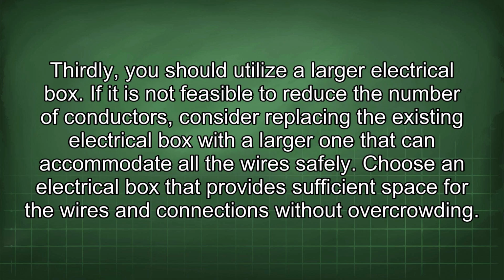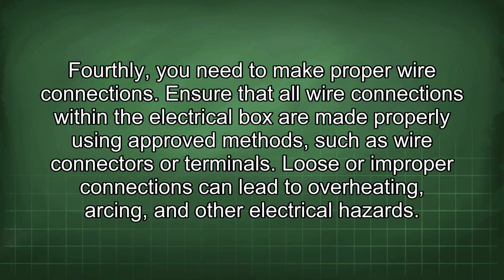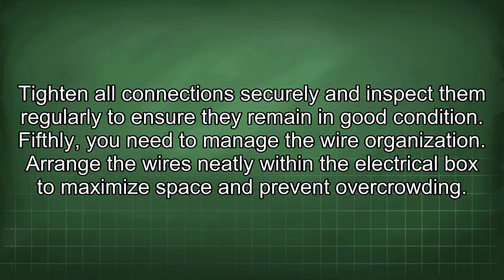Thirdly, you should utilize a larger electrical box. If it is not feasible to reduce the number of conductors, consider replacing the existing electrical box with a larger one that can accommodate all the wires safely. Choose an electrical box that provides sufficient space for the wires and connections without overcrowding. Fourthly, you need to make proper wire connections. Ensure that all wire connections within the electrical box are made properly using approved methods, such as wire connectors or terminals. Loose or improper connections can lead to overheating, arcing, and other electrical hazards. Tighten all connections securely and inspect them regularly to ensure they remain in good condition.